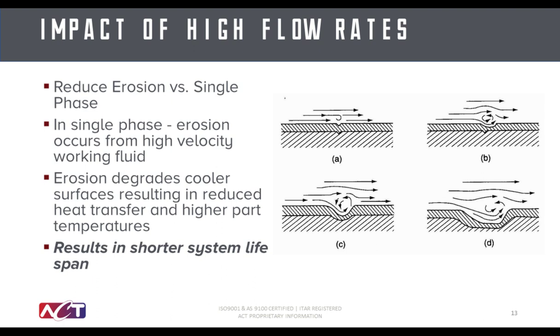If you do try to send single-phase fluid at a high velocity through coolant channels, you run the risk of eroding the channel walls. This is particularly an issue in microchannel coolers for laser diode applications, where the very small hydraulic diameter of the channels results in very high velocities. As the single-phase fluid flows through the channel at high speed, it tears away at the walls of the channel, as you can see in the image on the right. Over time, the channel walls can deteriorate to the point where they no longer contain the fluid, which results in a failure. Pump two-phase systems with their much lower flow rate do not have this issue.